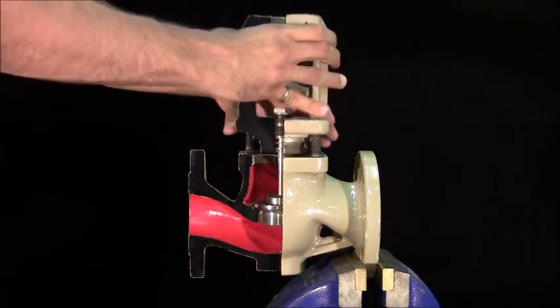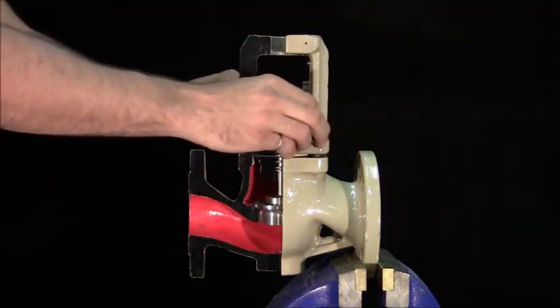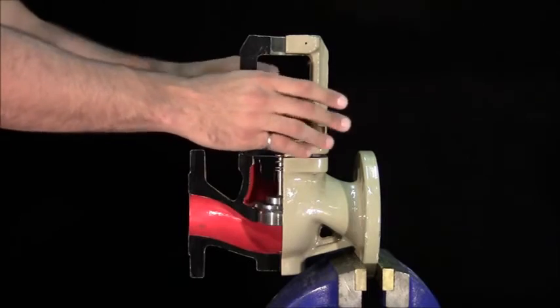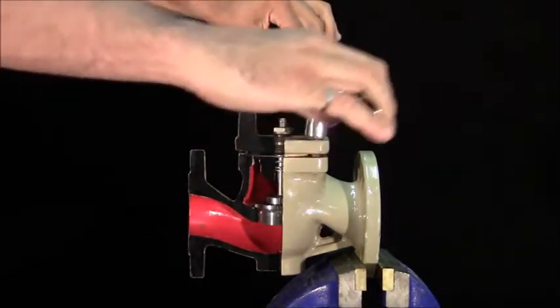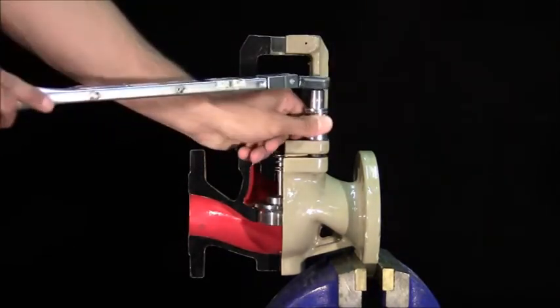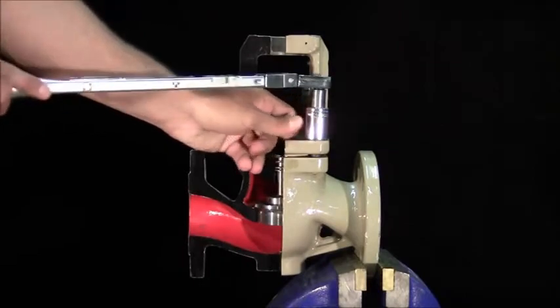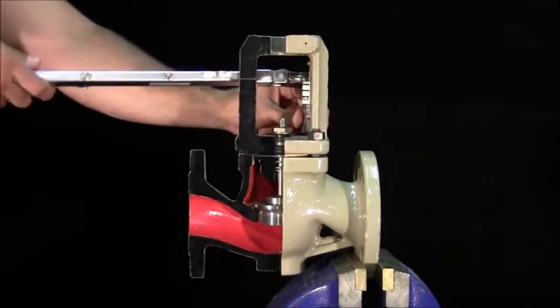The valve bonnet can now be carefully placed on the body. Install the nuts onto the studs until snug. A torque wrench will be used to tighten the nuts in a criss-cross fashion, tighten to 50% of the torque value and then again to 100%.